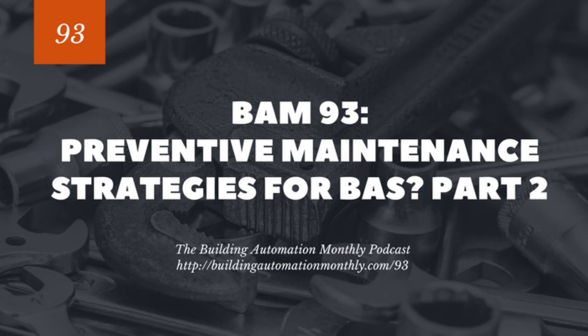You can have graphics that have everything on them. You just need to then have multiple graphics. You'd have a graphic for the mechanic, a graphic for the BAS tech, and a graphic for the facility operator or the maintenance guy. This would allow you to put the right points and the right systems on the graphics that only that person needs to know. Now, that becomes an administrative nightmare because you have to maintain three sets of graphics instead of one, but that's one way to do it. That's why I tend to prefer the middle of the road.